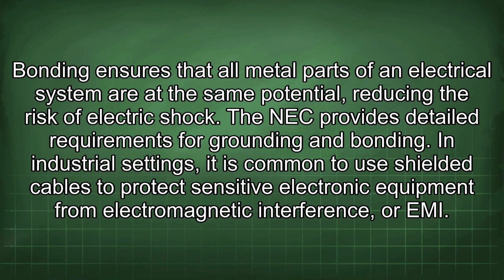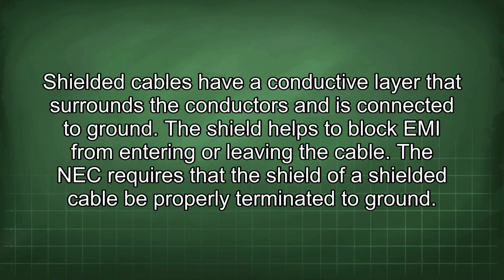In industrial settings, it is common to use shielded cables to protect sensitive electronic equipment from electromagnetic interference, or EMI. Shielded cables have a conductive layer that surrounds the conductors and is connected to ground. The shield helps to block EMI from entering or leaving the cable. The NEC requires that the shield of a shielded cable be properly terminated to ground.